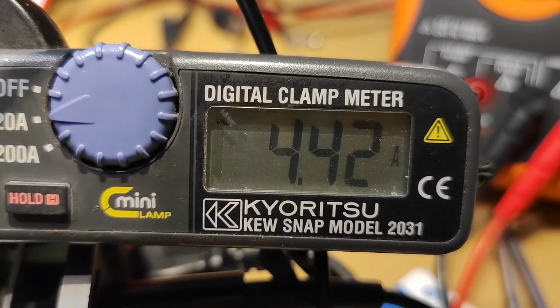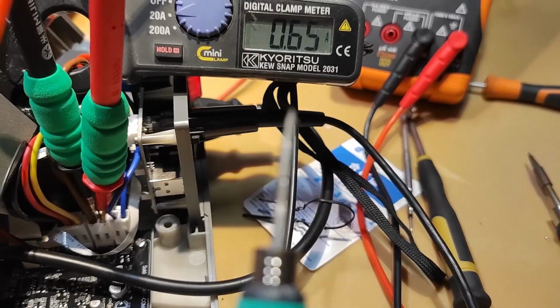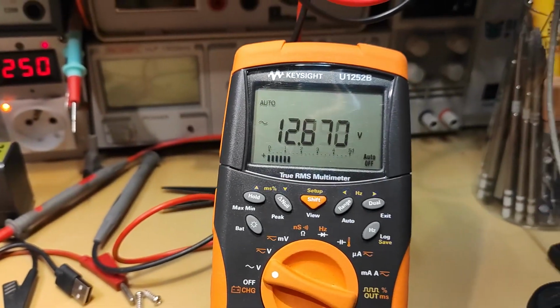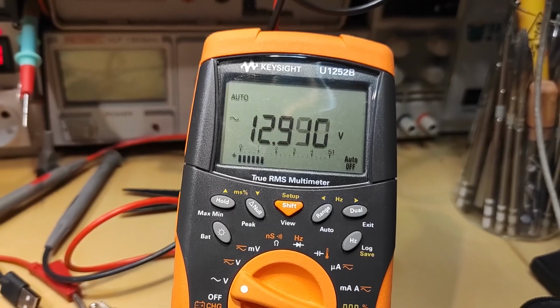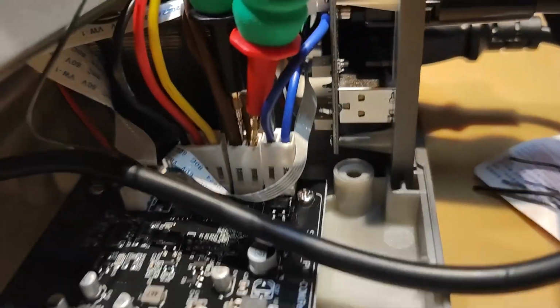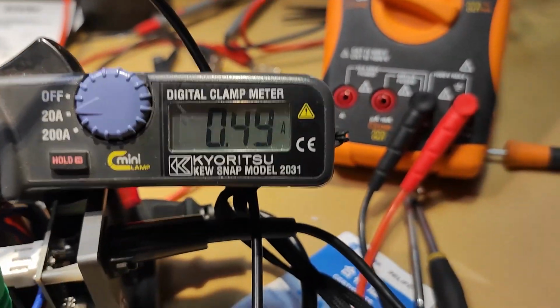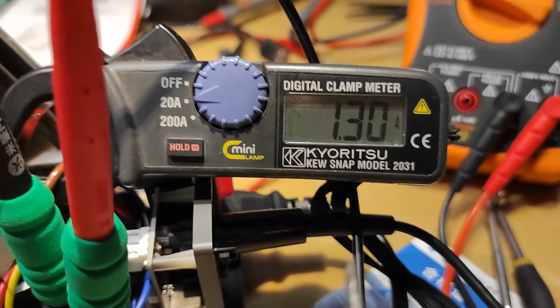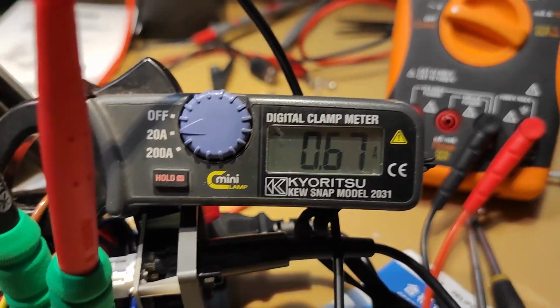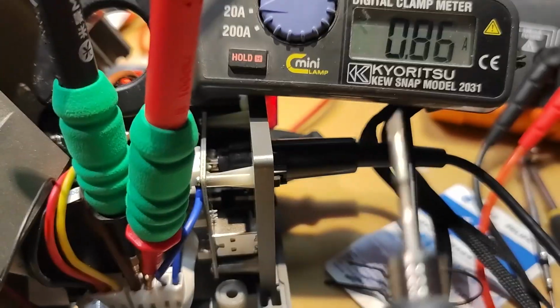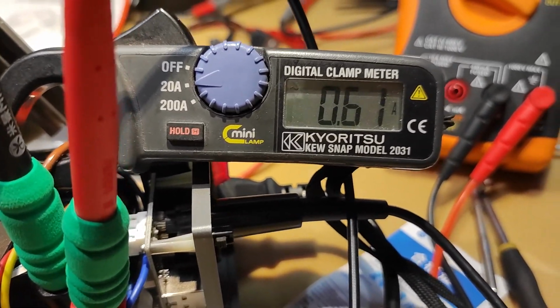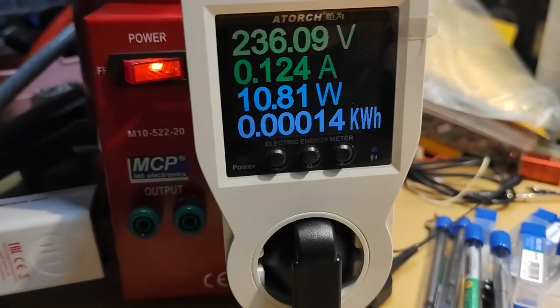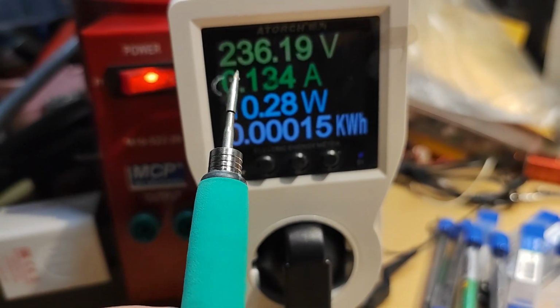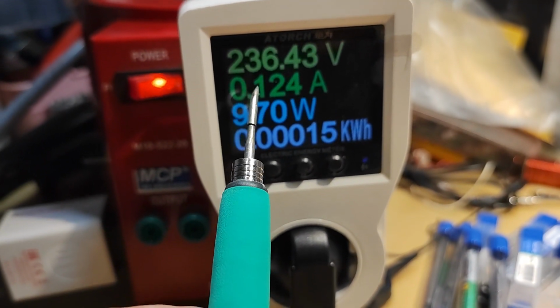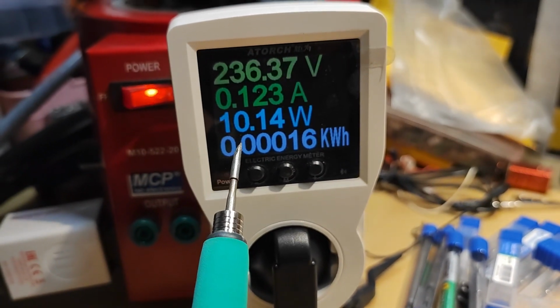Okay, you can see 4 amp for regulating this chip, and a voltage about 13 volts alternating on this brown wire. Also, if you want to check the intensity, the current on the blue wire doesn't change because the blue wire is not made to drive the handle, it's just for the PCB. So here you can see for 230 volts the power consumption.